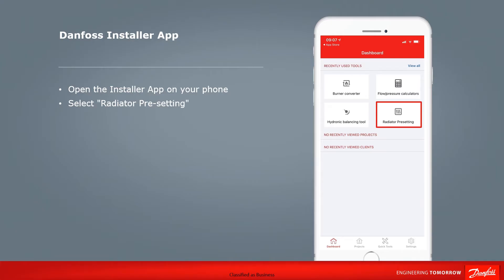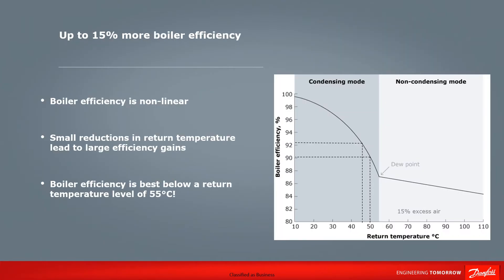With the Installer app open, please select radiator pre-setting to begin. Before we continue with the app, it's worth highlighting that boiler efficiency is non-linear. Small reductions in the return temperature can lead to large gains in efficiency. As you can see on the graph, modern boilers begin to condense with a return temperature of 55 degrees, giving an efficiency of around 86 to 88 percent. By reducing the return temperature by just five degrees, the efficiency increases to around 90 percent.